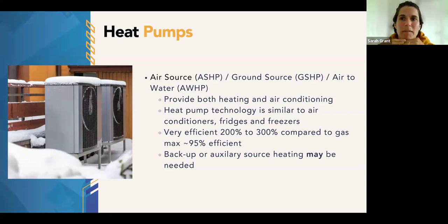So in this case, the costs to run a heat pump, as long as that auxiliary is not going to be running all winter at the same time as the heat pump, as long as that heat pump can do most of your heating requirement, and the auxiliary might be needed when it's really cold, then it's quite an affordable way to heat your home. Most of the homeowners that I've worked with who have that system, where it's a heat pump with an auxiliary, are finding they're saving a little bit each month. Nothing significant, not anything where it's worth calculating the ROI. Maybe it's like $10 a month in most cases, sometimes 14. I've heard someone say 8. So a little bit each month, but all that to say that they're very cost effective.